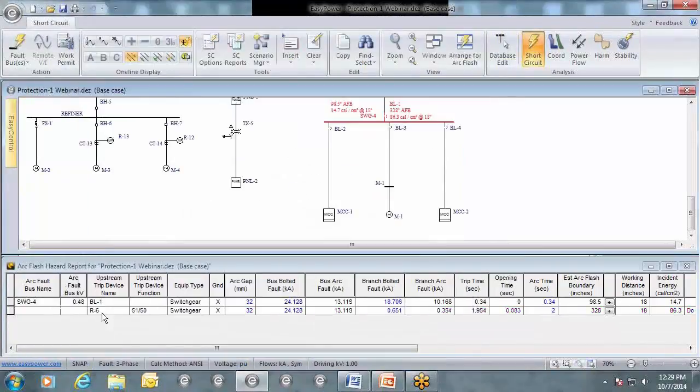you'll remember that our R6 was at approximately 2.7 seconds, if I remember correctly. Now even though it continues, it drops at a time of 2 seconds. So that has reduced the incident energy to 86.3 calories. It has not affected the including result because it's still only 0.34. It's only if it goes above that max time that you could specify that result.